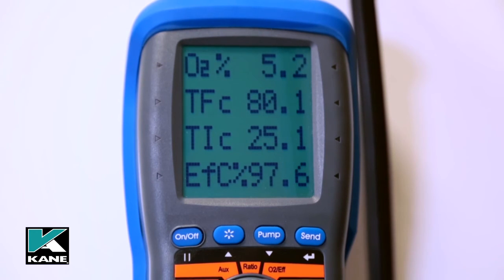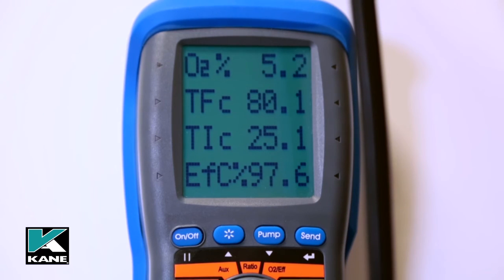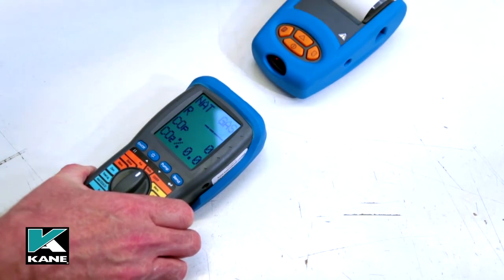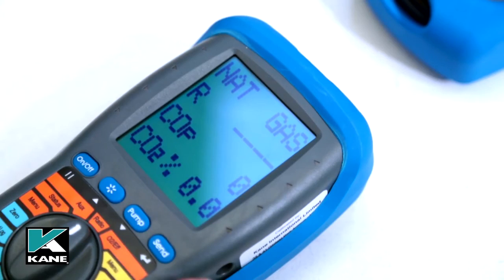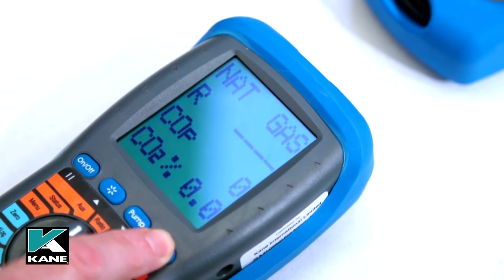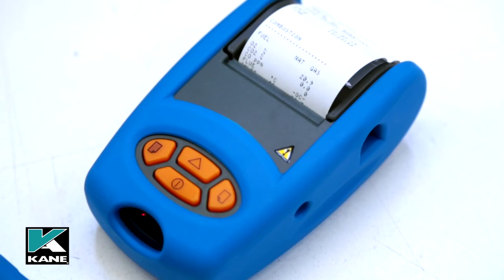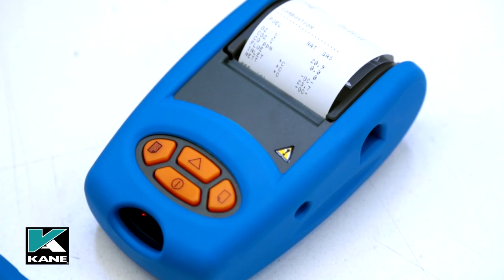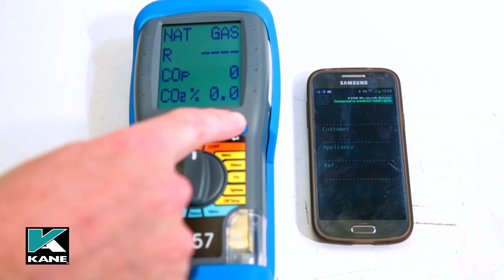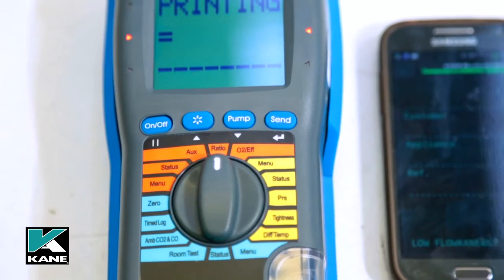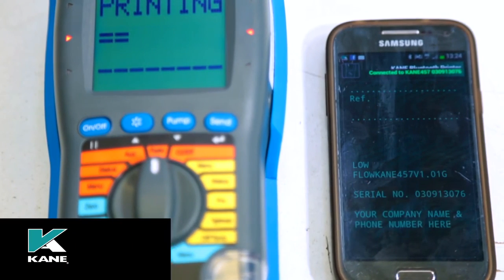If during the previous ratio test you saved the results, the O2 efficiency readings are also saved. To print a reading, align the printer to the analyser as shown. Make sure the printer is switched on, and a short press of the send key will transmit the readings to the printer. The printout will be a full combustion report including ratio, flue temperatures, losses, and excess air — everything needed for a full combustion report. If the optional Bluetooth module is fitted, these readings can also be sent to a PC or Android phone.